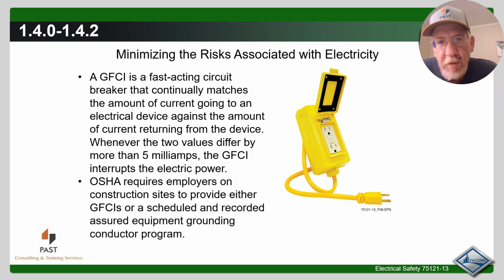There are two main methods of protection against electrical hazards, and they are insulation and grounding. A GFCI is a fast-acting circuit breaker that continually matches the amount of current that is going to an electrical device against the amount of current that is returning from the device. Whenever the two values differ by more than 5 milliamps, a GFCI interrupts the electric power. Now, OSHA requires employers on construction sites to provide either GFCIs, or they have to have a scheduled and recorded assured equipment grounding conductor program.